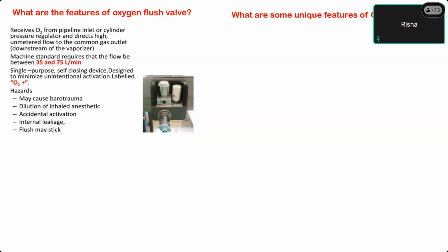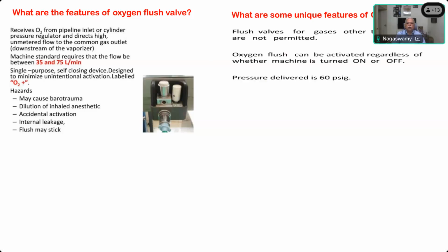They can operate even when it is off, since they are located upstream. Flush valves for gases other than oxygen are not permitted, so we have a flush valve only for oxygen. The oxygen flush can be activated regardless of whether the machine is turned on or off. Even when your workstation is in the off position with the power supply, it can still work. And pressure delivered is 60 psi. That is why barotrauma is very common, so unless really needed, we should not use this. Okay? So three things: it is unique for oxygen, it can work even when the machine is not on, and it is delivered at 60 psi pressure.